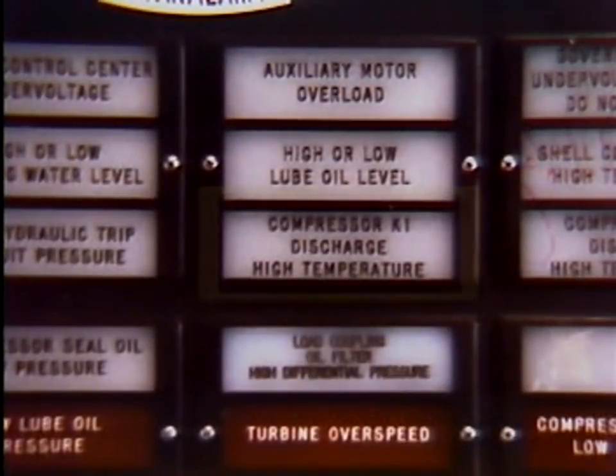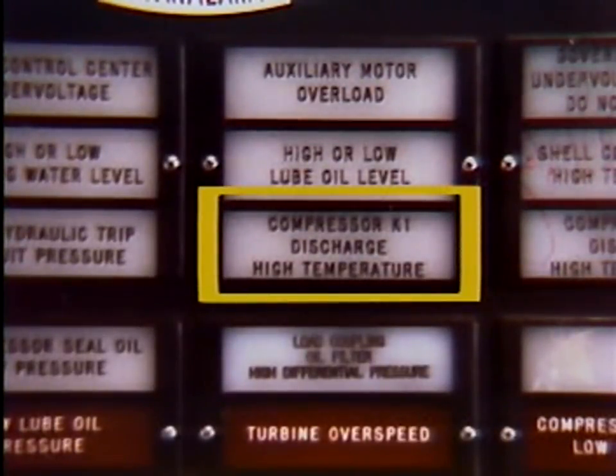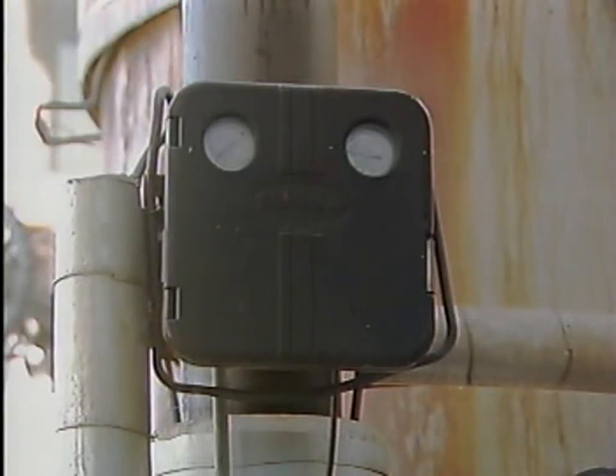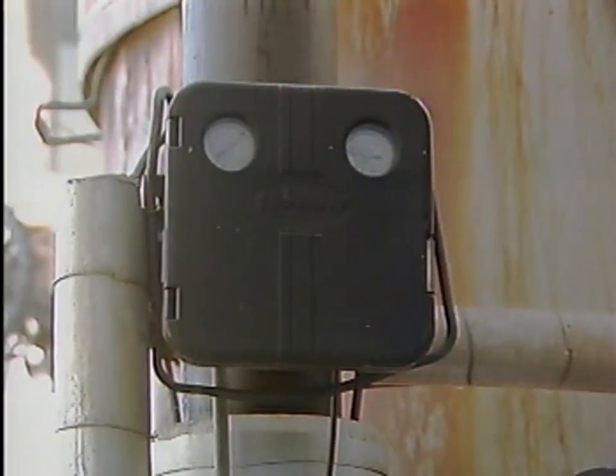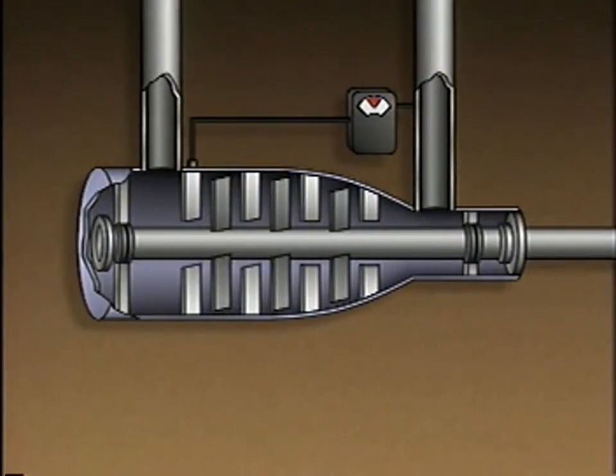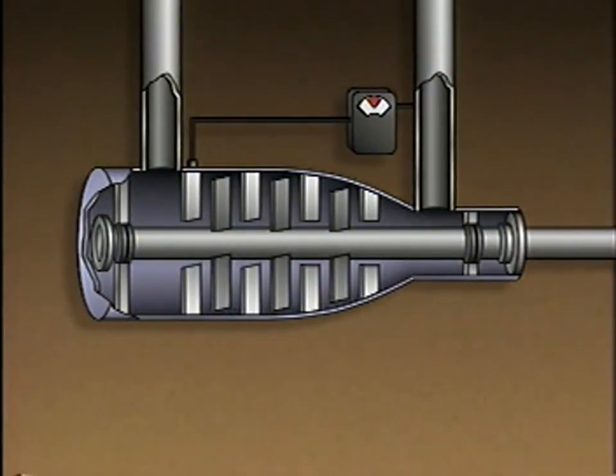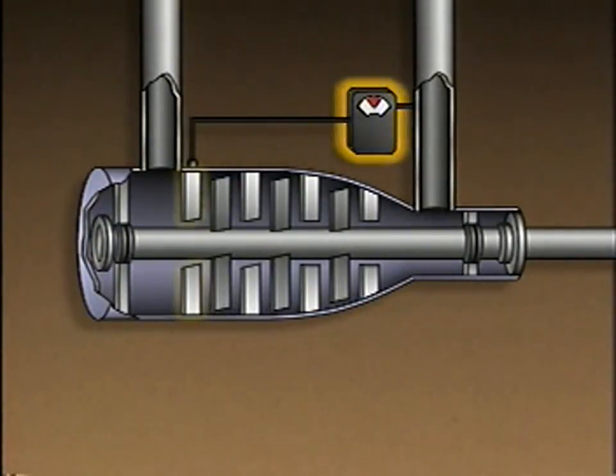For instance, this alarm is for high gas temperature. Compressor instrumentation and control devices also maintain the gas discharge pressure. This simplified illustration shows an axial compressor with one type of control system that maintains a constant discharge pressure. The main components of this control system are a pressure controller and inlet guide vanes.